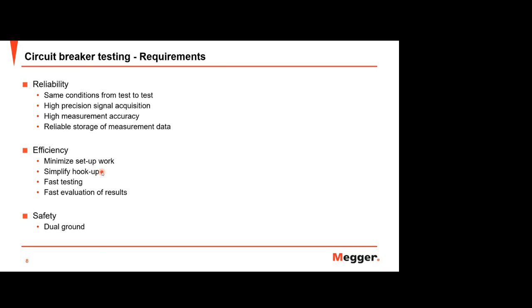And of course, high accuracy signal acquisition is also necessary. You need a better instrument to test your asset to get more valid results with high measurement. So these are some requirements that are very commonly considered when we want to choose the instrument for testing your circuit breaker.